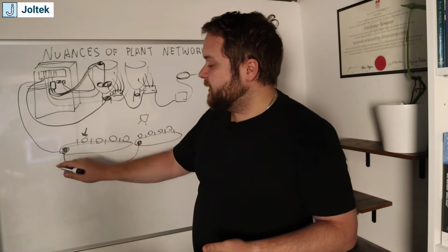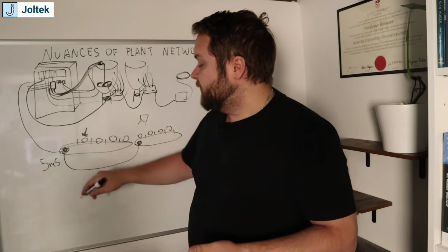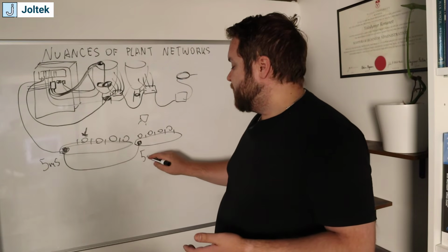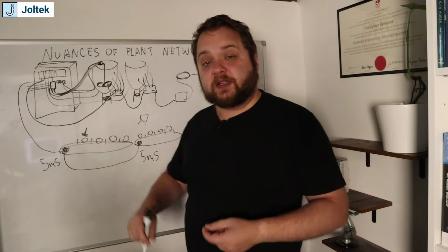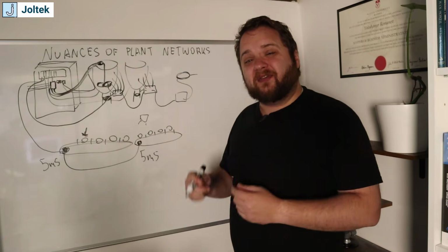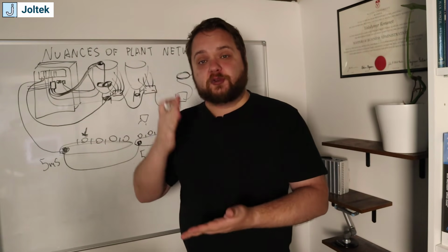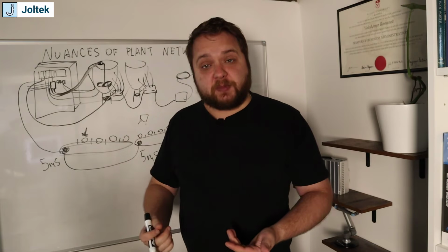And so the PLC, every 5 milliseconds, this drive is expected to have an updated reference for where it needs to go. The same happens with this one. Every 5 milliseconds, that network is sending out the position for the drive, and so it is very repeatable.